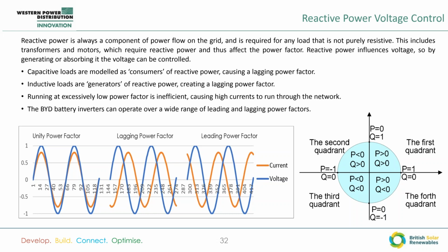Now we come on to the more complex reactive power control. So briefly, active power is the power that does work, and reactive power is just essential to the network. It's caused by transformers and capacitors on the network. And ideally, you try and keep the power factor, the ratio of active to reactive. You want as much active as you can and the absolute minimum of reactive power, because that's the most efficient way to use your assets.